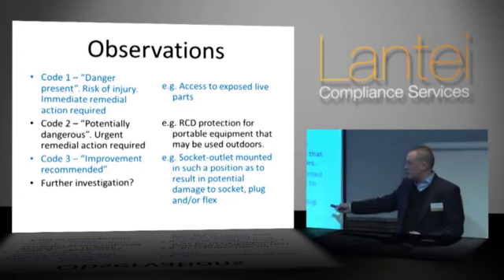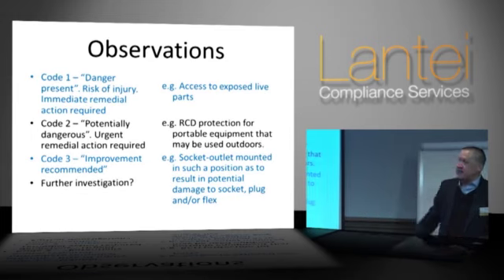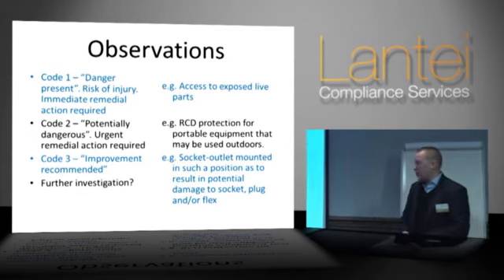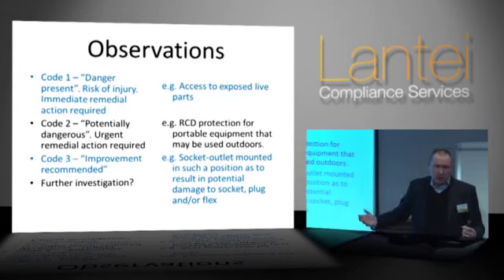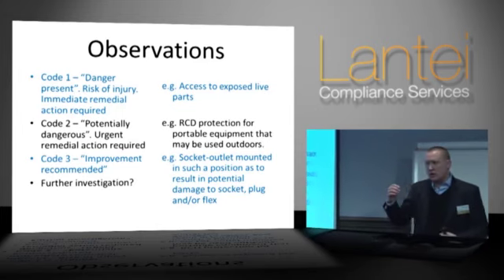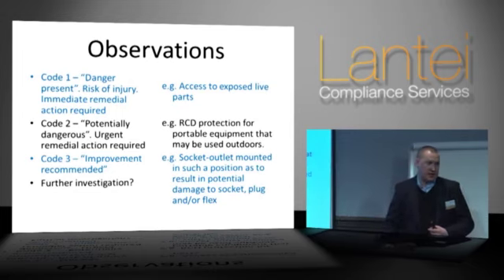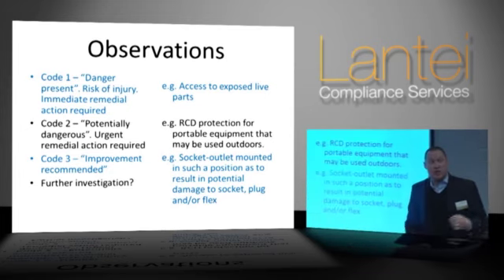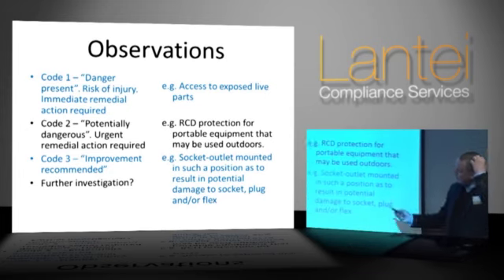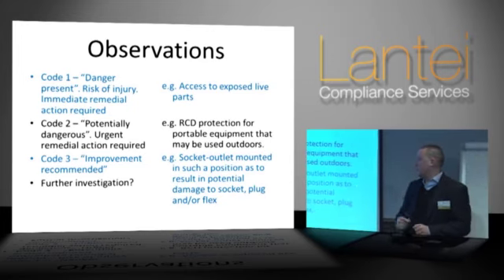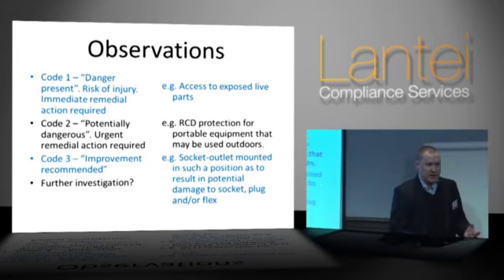The difference with the C2s and the C3s is that C3s are more there for looking at issues that need improving, but also issues that are being highlighted by new editions of the wiring regulations, okay? Because we're taking into account safety improvements that need to be made. So the example here, a very quick one: a socket outlet mounted in such a position as to result in potential damage to the socket and/or the flexible plug, i.e. it's too close to a work surface.